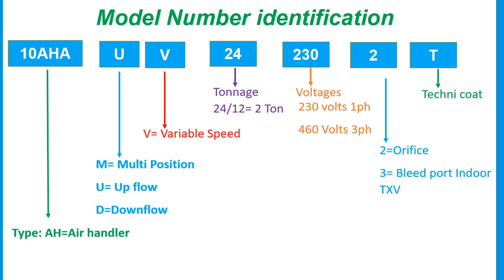The next digits, 230, indicate voltage — 230 volts, single phase. If it were 460, that would mean 3-phase power. The next character indicates phase — 2 or 3. Finally, TXV stands for thermostatic expansion valve, and 'T' represents Techni coat.